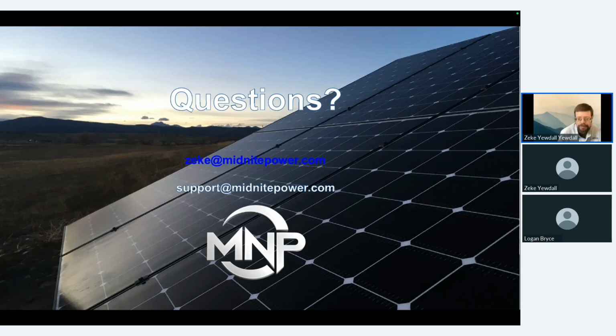Two things with regards to the grounding. Anywhere that's very distant from your point of neutral to ground bonding, which is usually in your main AC panel, your neutral and your ground have the potential of developing voltage between them during a lightning strike due to induced voltage. So if you're in a remote subpanel that does not have the neutral and ground bonded, because it's not the main service, you should actually have another lightning protector or surge suppressor between the neutral and the ground in that subpanel, because they are no longer definitely at the same potential.